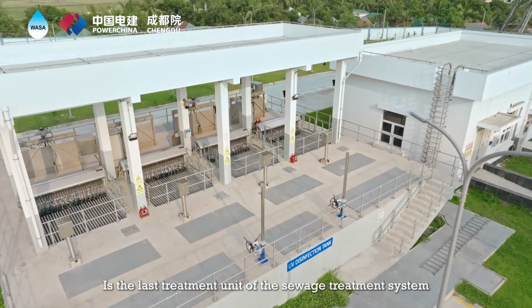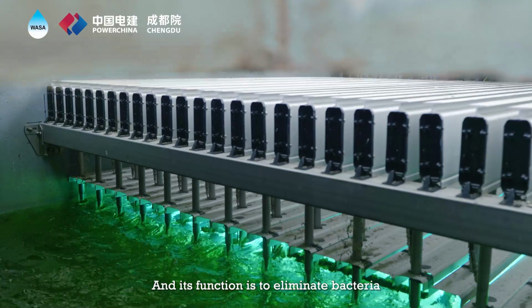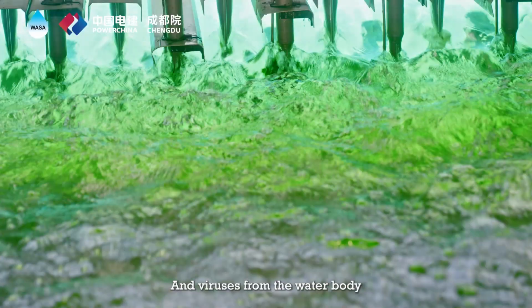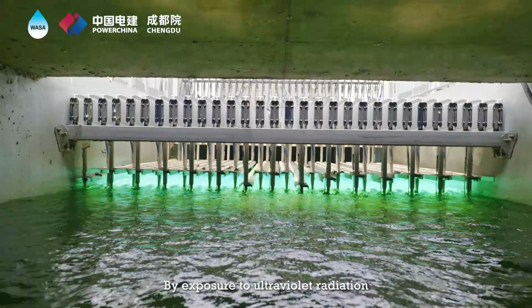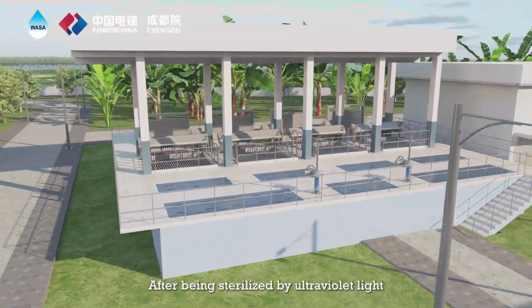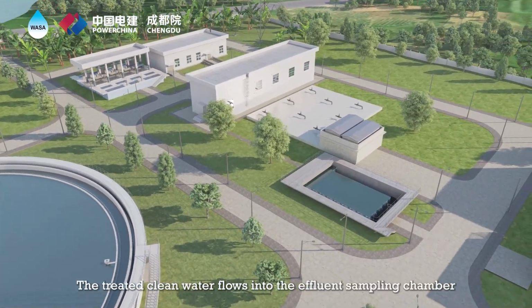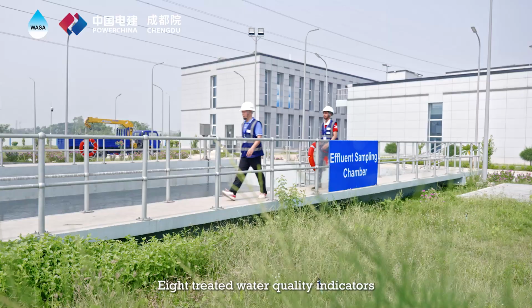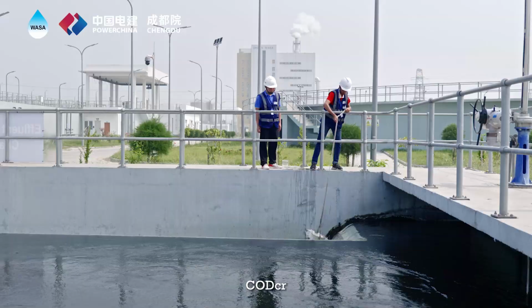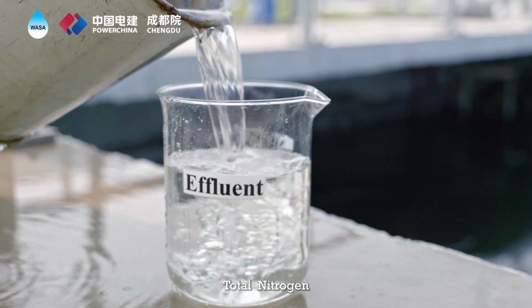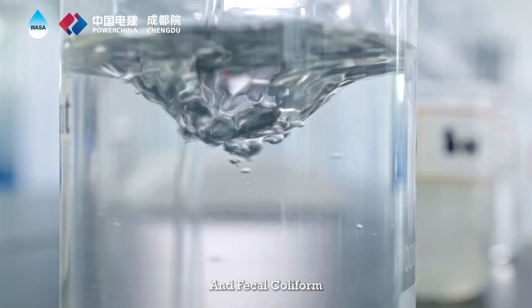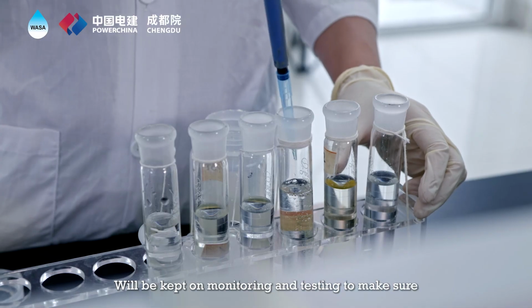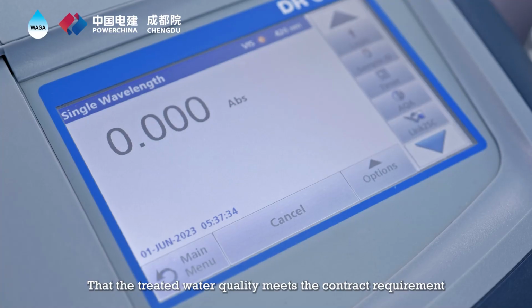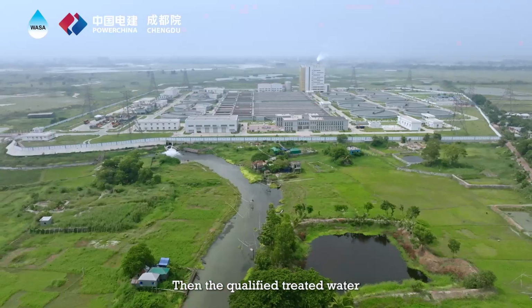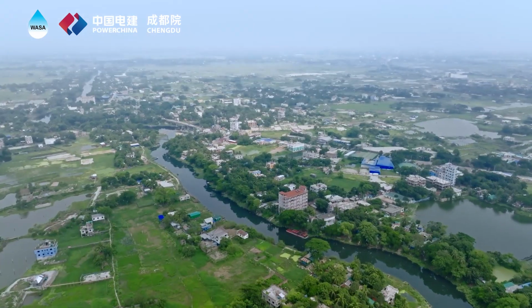Ultraviolet disinfection tank is the last treatment unit of the sewage treatment system, and its function is to eliminate bacteria and viruses from the water body by exposure to ultraviolet radiation. After being sterilized by ultraviolet light, the treated clean water flows into the effluent sampling chamber. 8 treated water quality indicators, including pH, COD, BOD, total nitrogen, suspended solid, phosphate, and fecal coliform, will be kept on monitoring and testing to make sure that the treated water quality meets the contract requirement. Then the qualified treated water will be finally discharged into the Gojaria Canal.